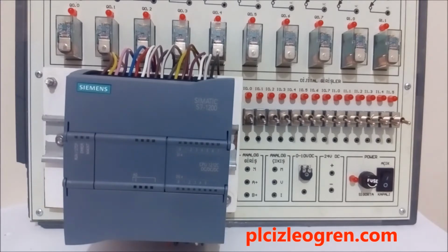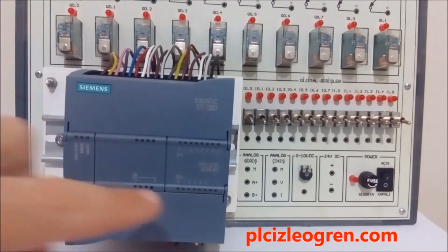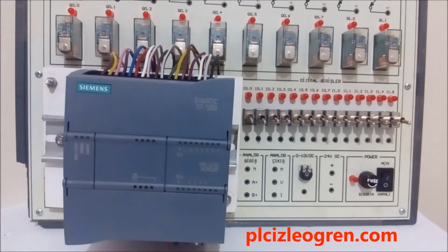Now, let's explain relay output and transistor output. You can't perform fast on-off switches using relay output PLCs. These have small 2 ampere relays. If I'm not remembering it wrong, we are going to need to look at the catalog. These relays, after all, are mechanical. On-off speed can't be as fast as a transistor.